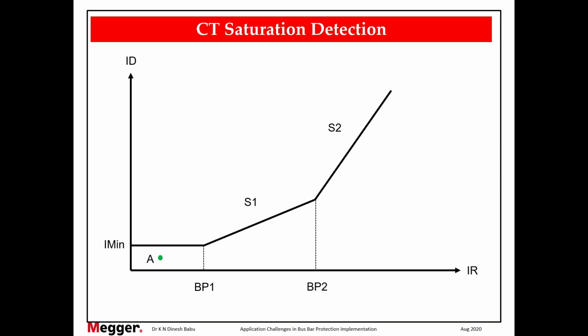We are going to use a lens, and you are going to zoom in. So let us see every millisecond, every nanosecond, what is happening after the fault occurred. Your full load current is 1 per unit. Let us assume at 3 per unit your CT is going to get saturated. So from 1 per unit, in 1 nanosecond it is not going to become 3 per unit. It will increase 1 per unit, 1.01 per unit, 1.02 per unit, 1.03, etc., up to 2.5 or 3.